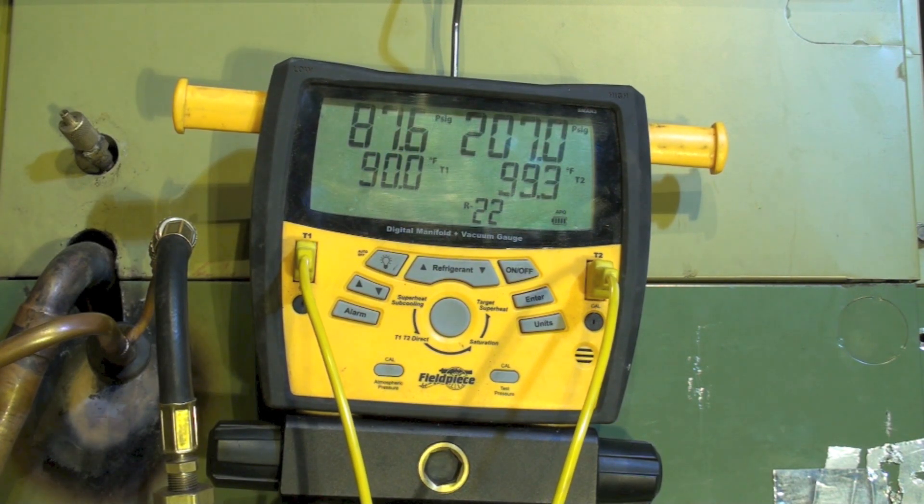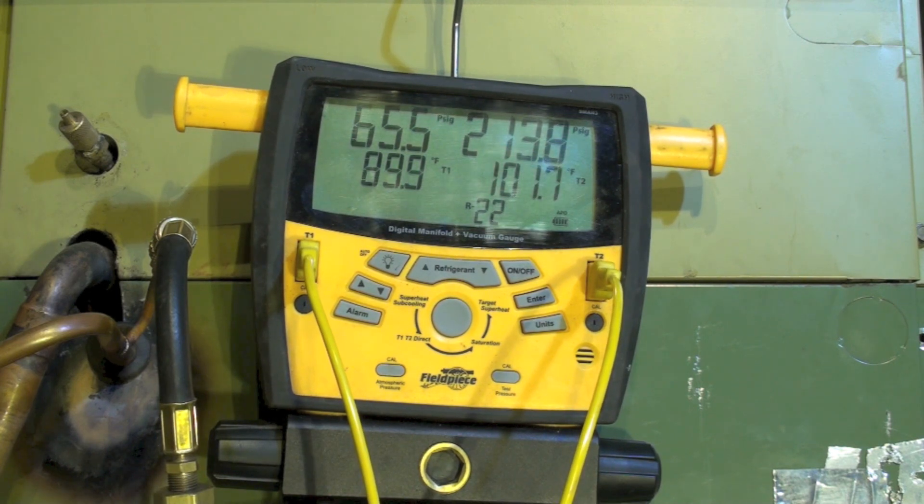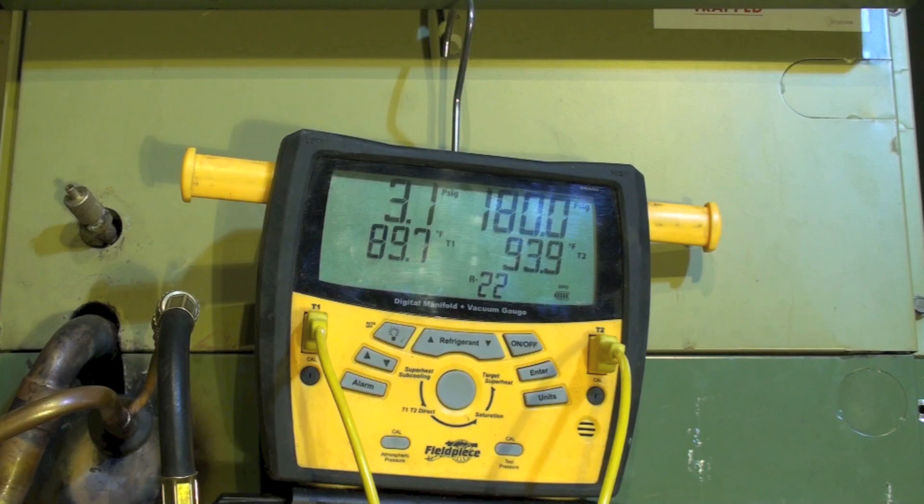Hey, obviously we have the compressor running and you can see we're dropping on our suction. Now it's getting slow on its pull down. Right now that does not seem to be the compressor. I've got frost on my accumulator.